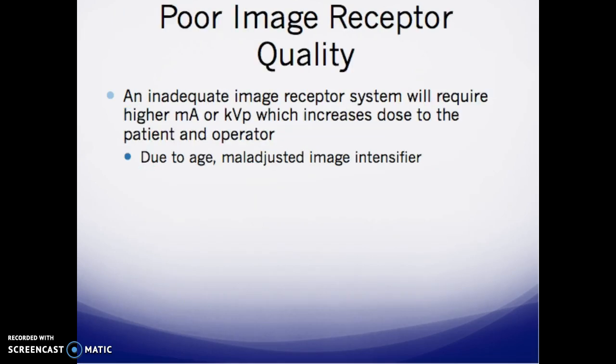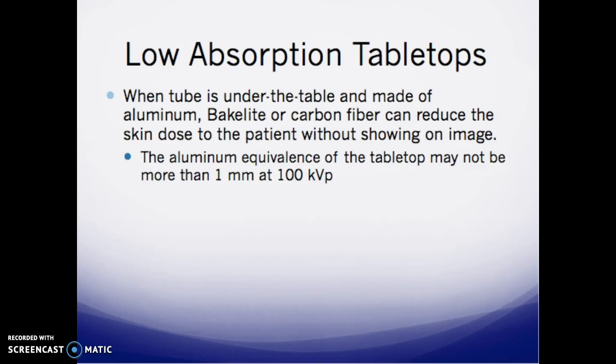Poor image receptor quality: an inadequate image receptor system requires higher MA and KVP, which increases patient dose. This occurs due to age and malalignment of the image intensifier. Low-absorption tabletops — made of aluminum or carbon fiber when the tube is under the table — can reduce skin dose to the patient without affecting image quality. The aluminum equivalence of a tabletop may not exceed 1 millimeter at 100 kVp.